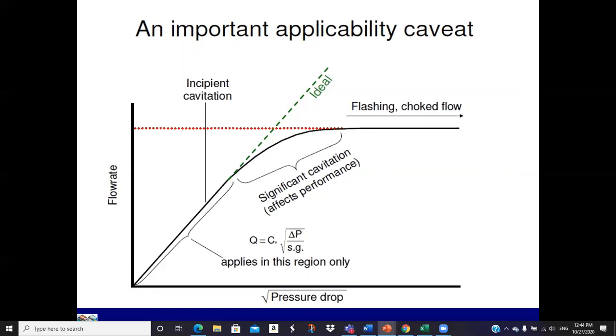Well, I'll actually pull it up here. This equation, Q is CV times the square root of delta P over specific gravity, is only good for a while. If we look at flow rate and the square root of pressure drop, basically this is linear up to the point that we start to get cavitation, which means that the pressure gets so low that we start forming vapor bubbles inside the valve and on the exit of the valve. If that gets too bad, we get what we call choke flow, which means that it doesn't matter what the stem position is, we can't get any more flow out of it. So this is called choke flow. This is an ideal condition, and it happens for a while, but it doesn't happen forever.